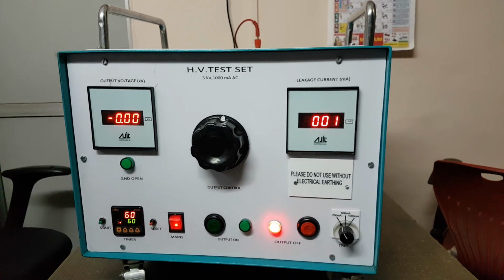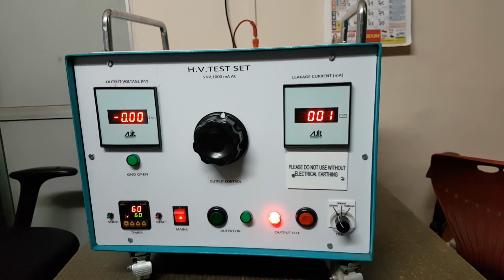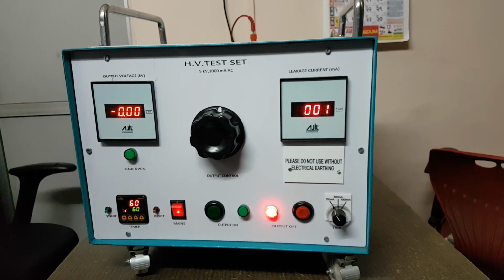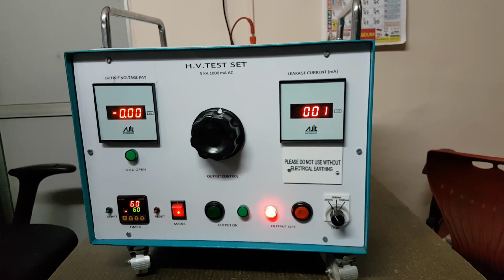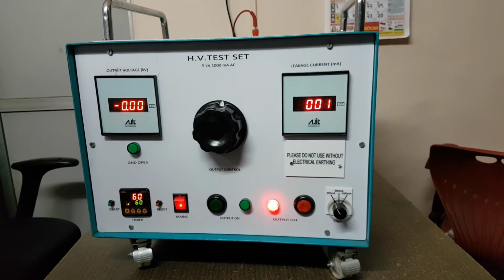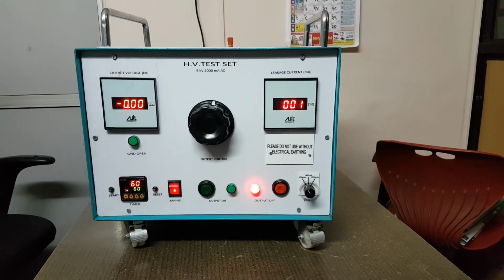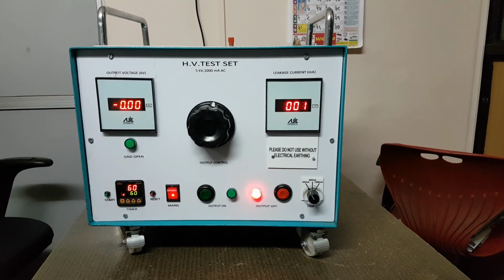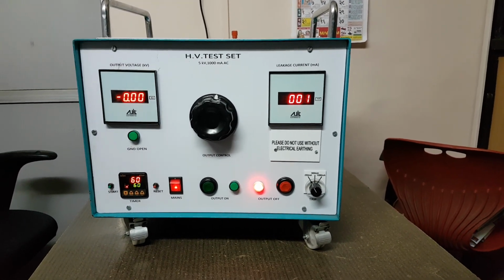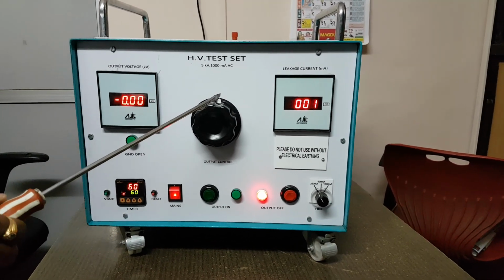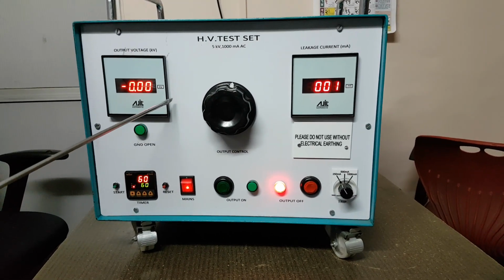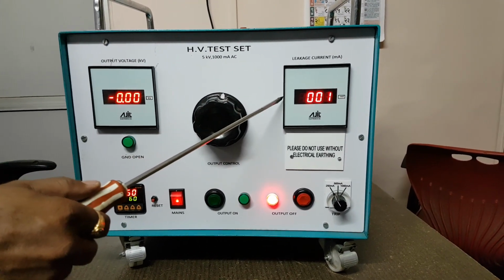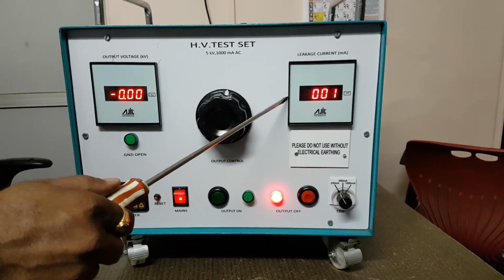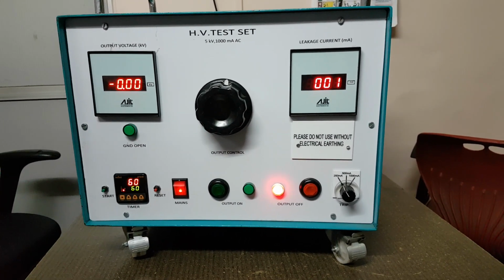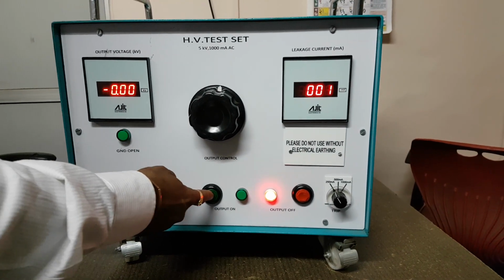This is the output tripping facility on the high voltage when overcurrent happens or the object under test fails. Now we have seen the output overcurrent tripping facility which is provided in the instrument. Now we will see the function. As I said, this is the output control knob, this is the high voltage output kV meter, and this is the leakage current meter. Just now we saw the leakage current or the output current on the meter. Now we will see the voltage.